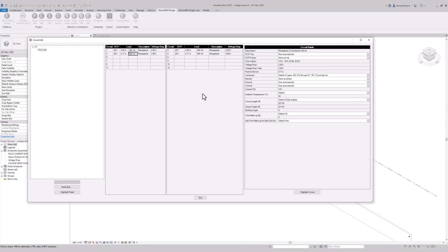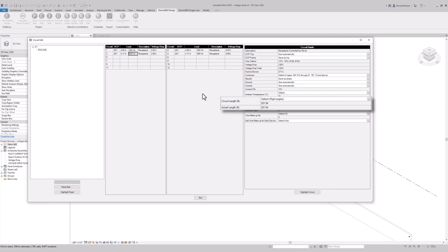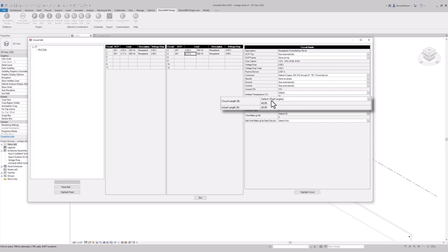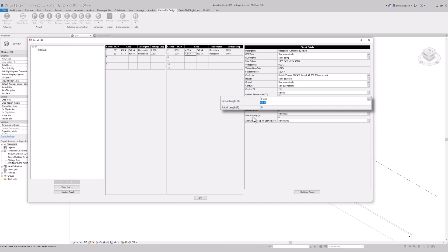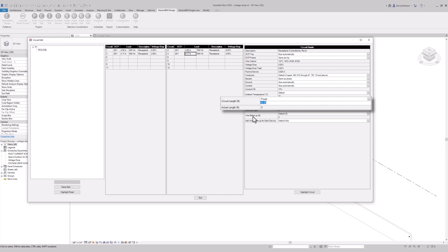If you look at these two circuits in ElectroBIM, you can see that our software is seeing different lengths for them — the first circuit is 200 feet and the other circuit is about 50 feet. We do also allow you to override that. We let you calculate it a couple of different ways, including using that circuit length that Revit has calculated. We also have the ability to do a fixed length where you can specify what the length should be, so if for any reason you want to do your calculation using a different length, you can just type it in.